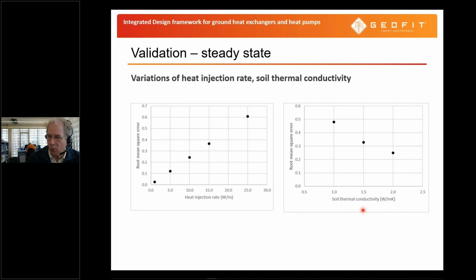Here we looked at the soil thermal conductivity, and again, not very surprising, if the soil thermal conductivity increases, the error decreases, because obviously the temperature change near to the Earth baskets will be smaller as well. But again, we can see that in the range that we expect for an Earth basket, which will normally be installed in slightly saturated to unsaturated soils with a soil thermal conductivity not higher than 2 and more likely to be between 1 and 1.5. Again, the root mean square error between the CFD and the analytical solution is relatively small, between 0.5 and 0.3 Kelvin.